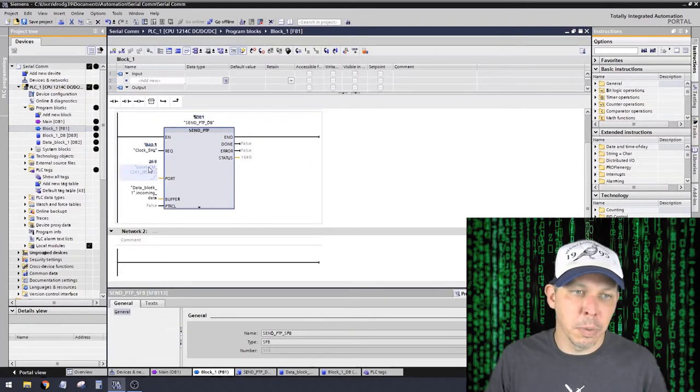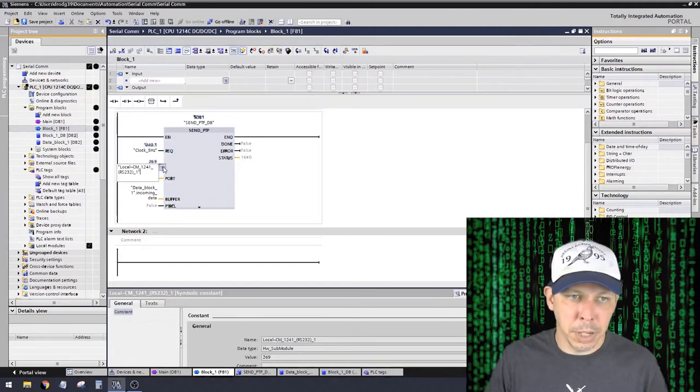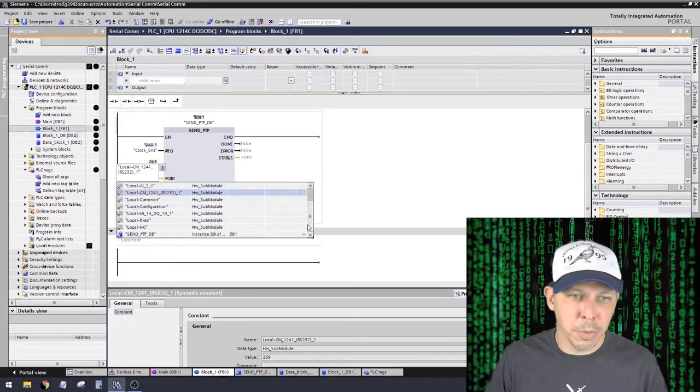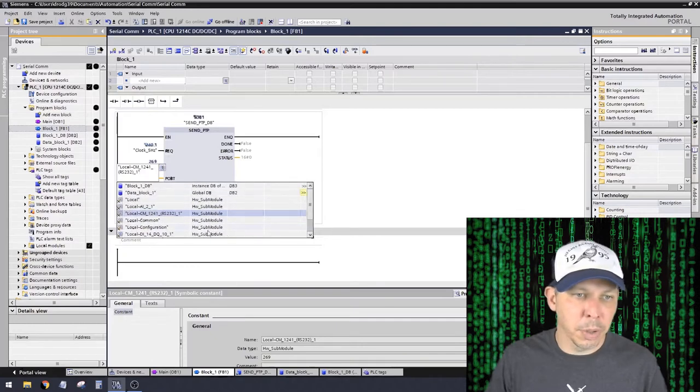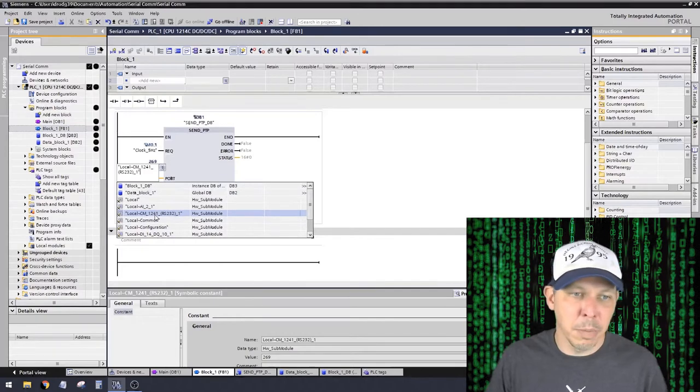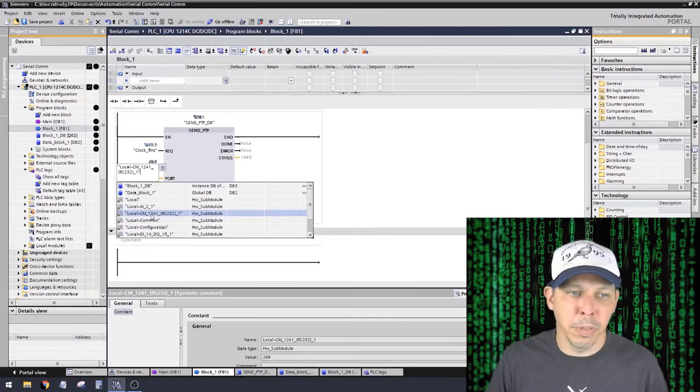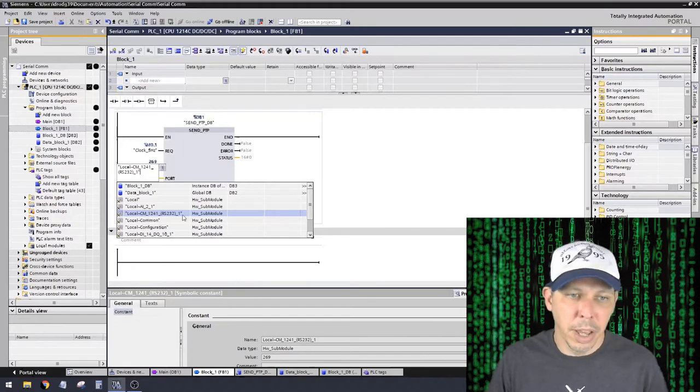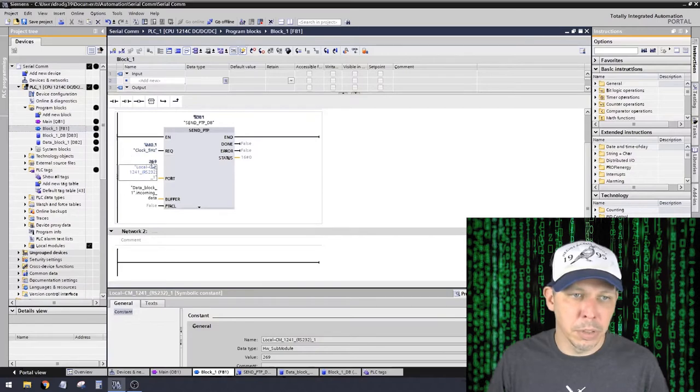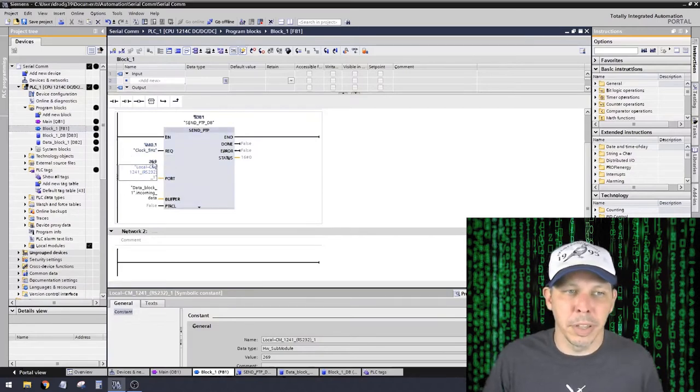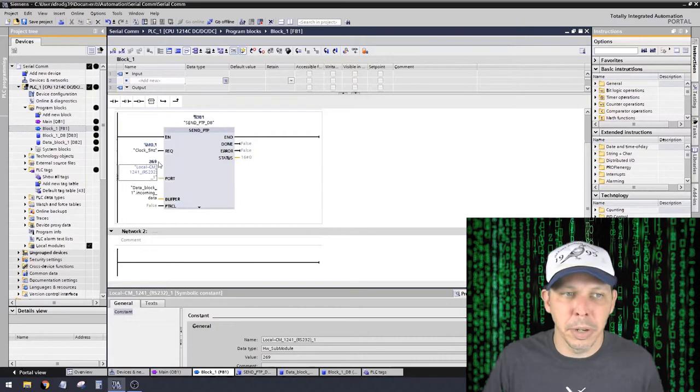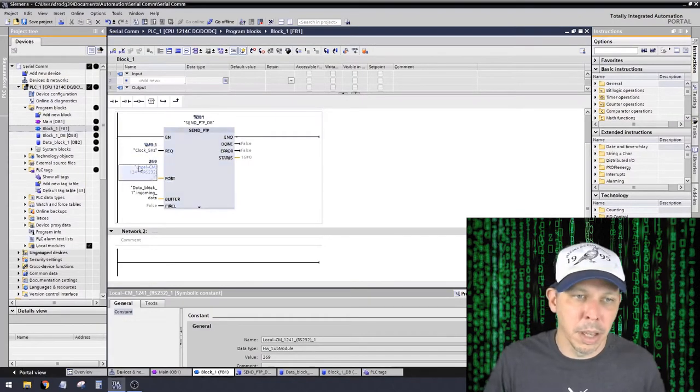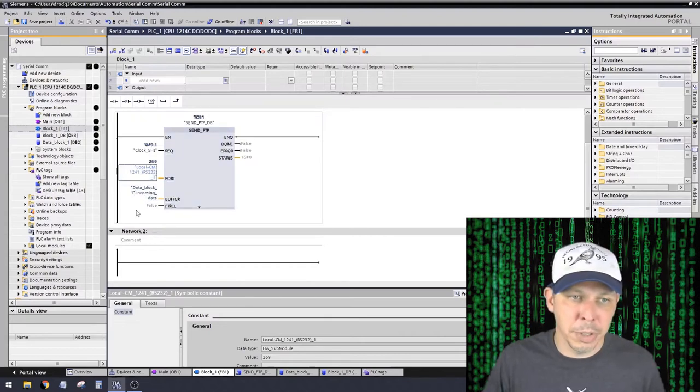So this is switching states 5 times a second. 5 times a second, it's telling this function block to look at what's in the buffer and send it. And this is the port that it's on. So it'll be blank when you first put this function block in here, and you'll click on here and have a pull-down list of all your options. And the one that says RS-232, and it says CM1241, that's the name of the module. And then here's my buffer. This is what actually is going to be sent.